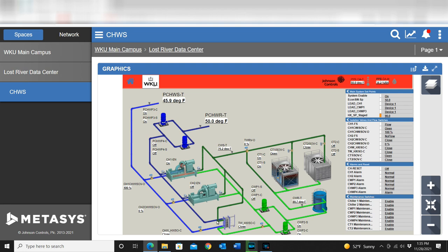You should be aware that during the switchover period of this system from going back from the chiller to the plate frame, of course, this system is isolated out. There are valves that keep water from flowing through this. And that's done for a few reasons. One is, if you're trying to run water through these the entire time, you're going to be fighting yourself.